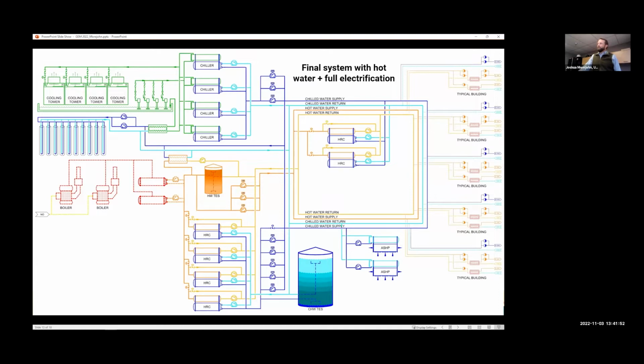We do heating because of our temperature swing. The boilers are going to stay as long as we need them, but ultimately they will be phased out and replaced with the full electrification plan - replaced with other sources of low-grade heat that we could use in the winter, running heat recovery chillers for all of our heating.